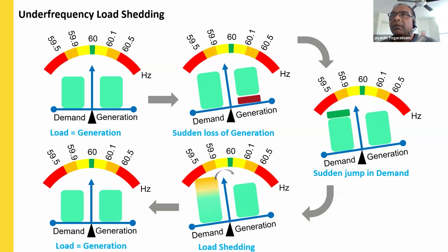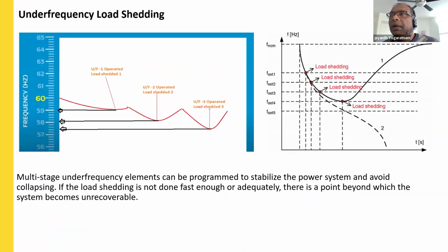When there is a deficiency in generation, due to a drop of generation or adding of sudden load, the frequency will come down. But by doing the load shedding, the frequency can be brought back up to stability. If you have multiple levels of under frequency element, you may be able to do multi-stage under frequency load shedding. And if the load shedding is not done fast enough or adequately, there is a point beyond which the system is unrecoverable. When we look at this particular curve, there are two curves here, curve number 1 and curve number 2. We always expect to follow curve number 1 after the four-stage load shedding.